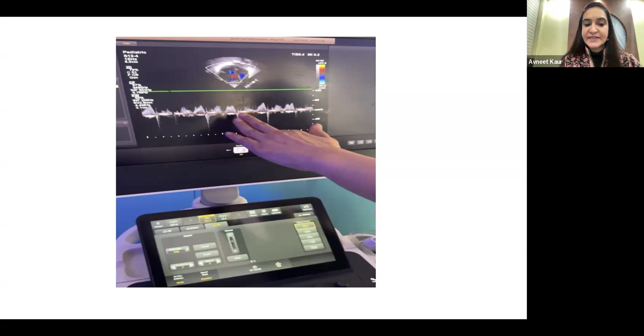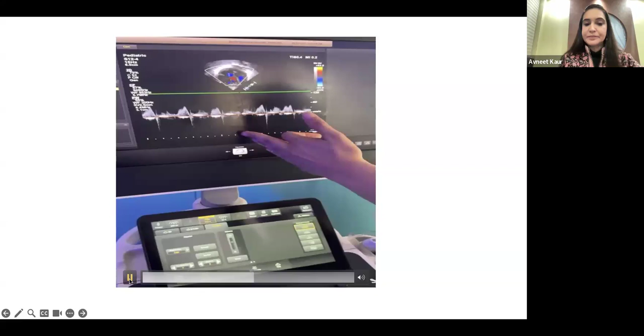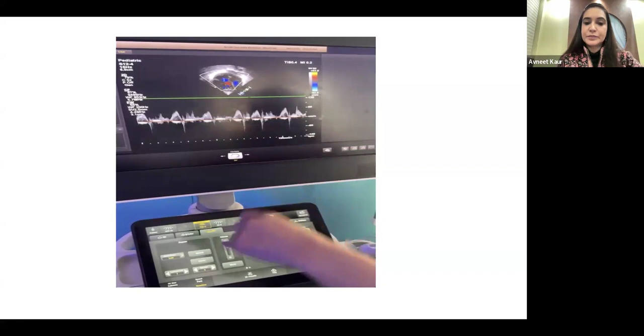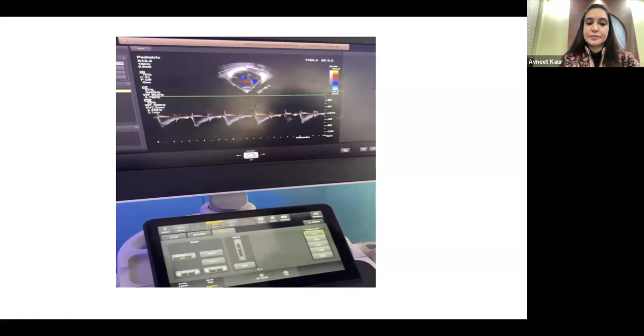Sometimes we are seeing images where the regurgitation lesion or the blood flow is more of blue flow. Then at times I have to adjust my scale up so that I can see my blue flow better, because that will be on the downside. And sometimes the velocity is higher, then I need to adjust my scale to maybe 100, 120, 140. Otherwise I will get something called the aliasing effect, that is my image will be cutting. So I need to adjust these four important parameters. Below the baseline will be the blue, which is away from the probe. But suppose I'm not able to see very well, then I can change my baseline so that I can visualize my flow better, either above or below. I've adjusted my baseline using this button.